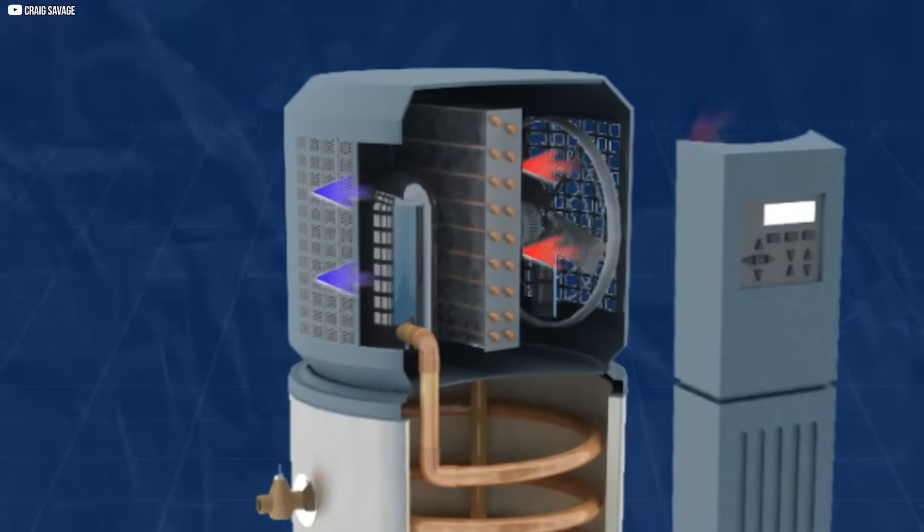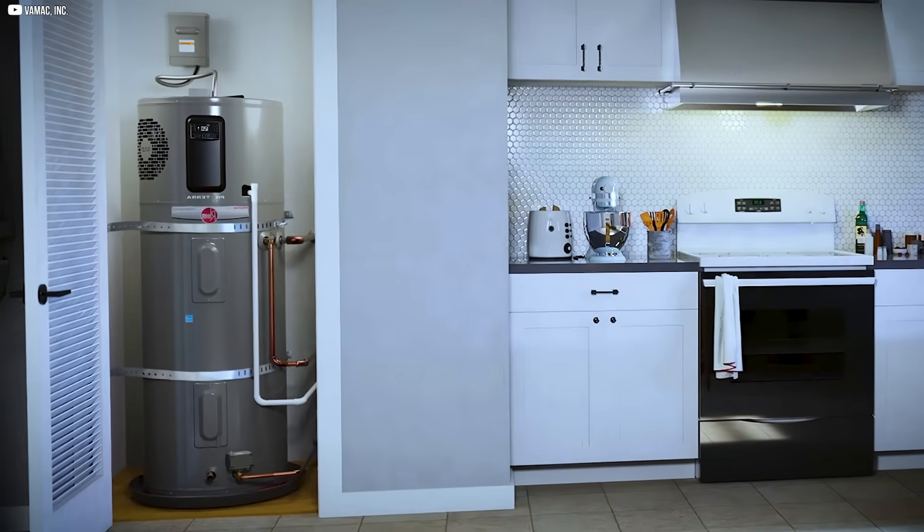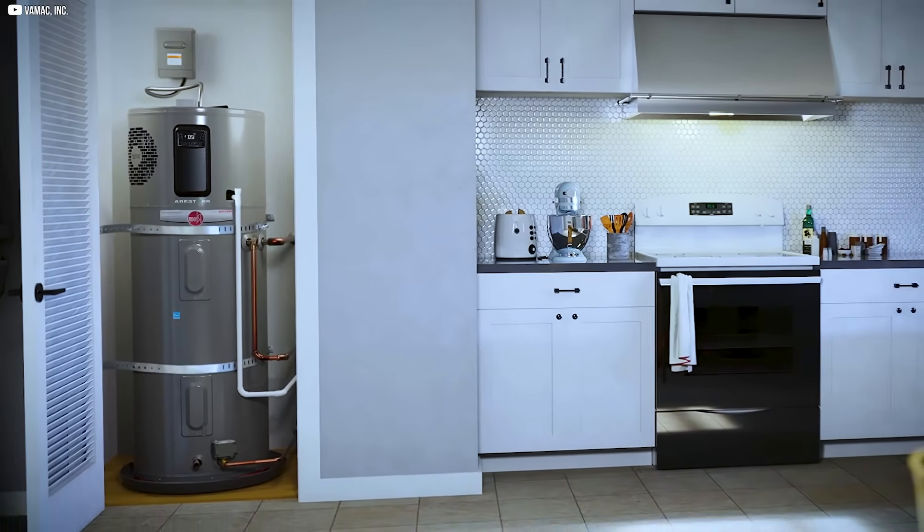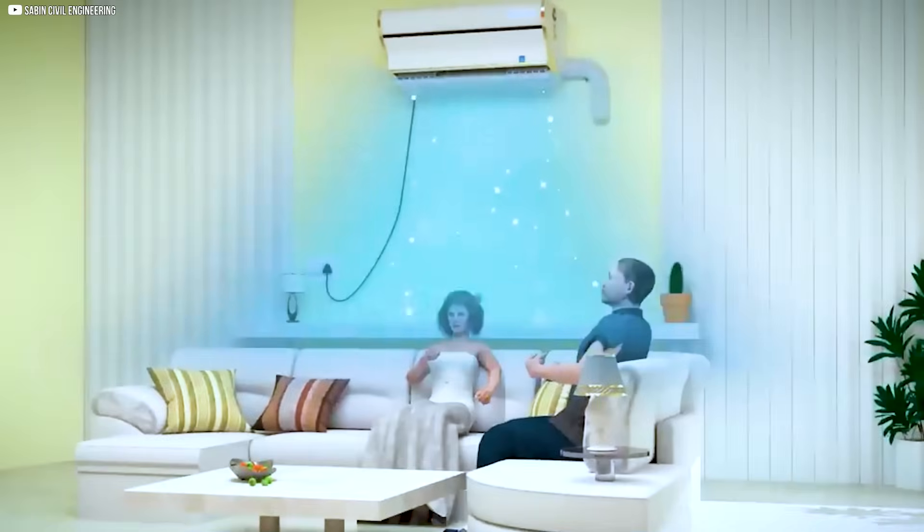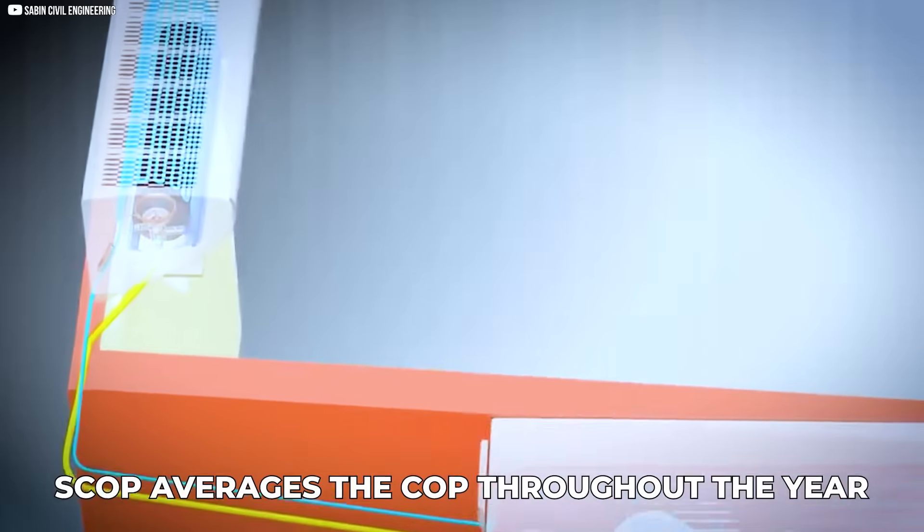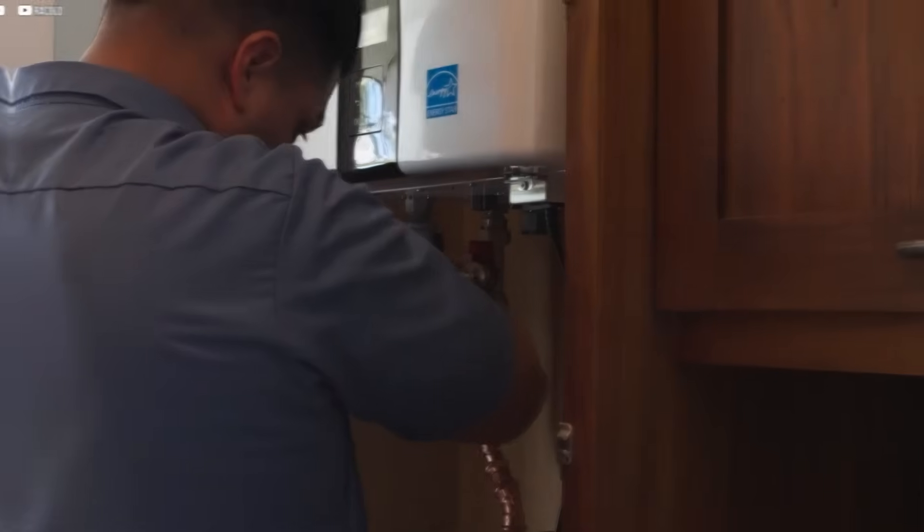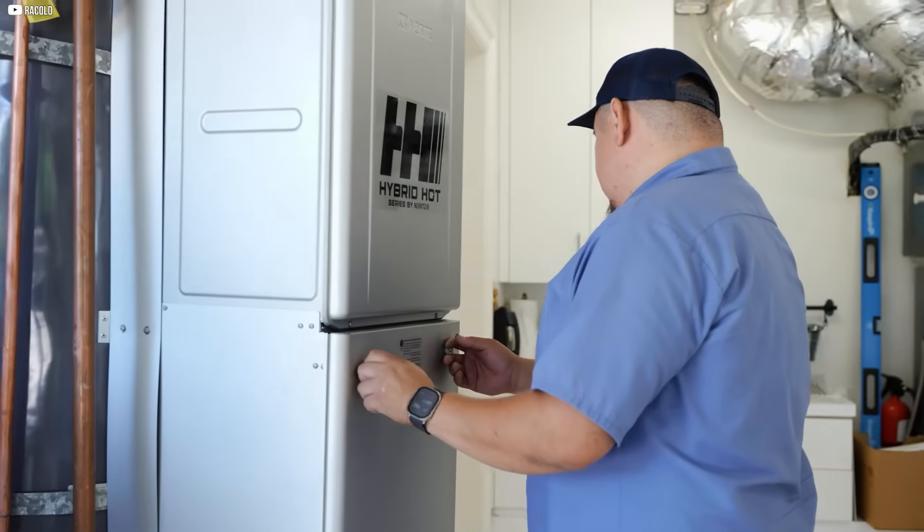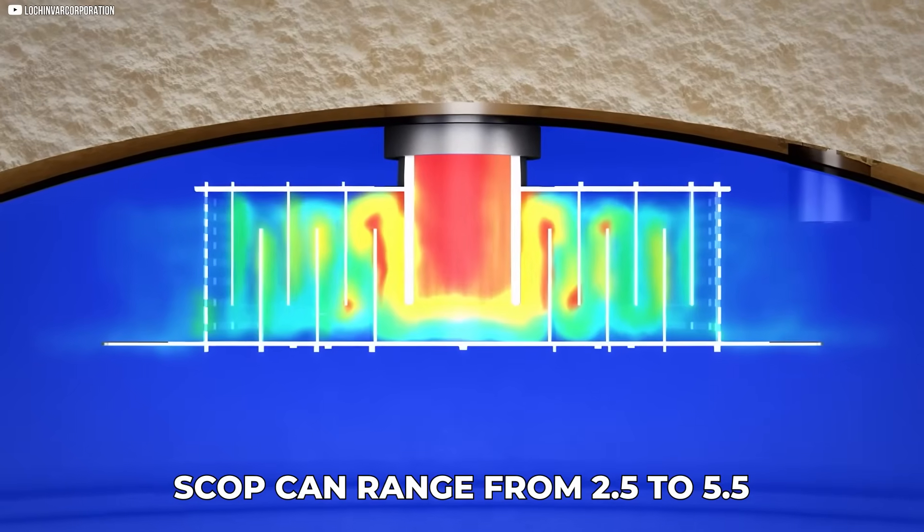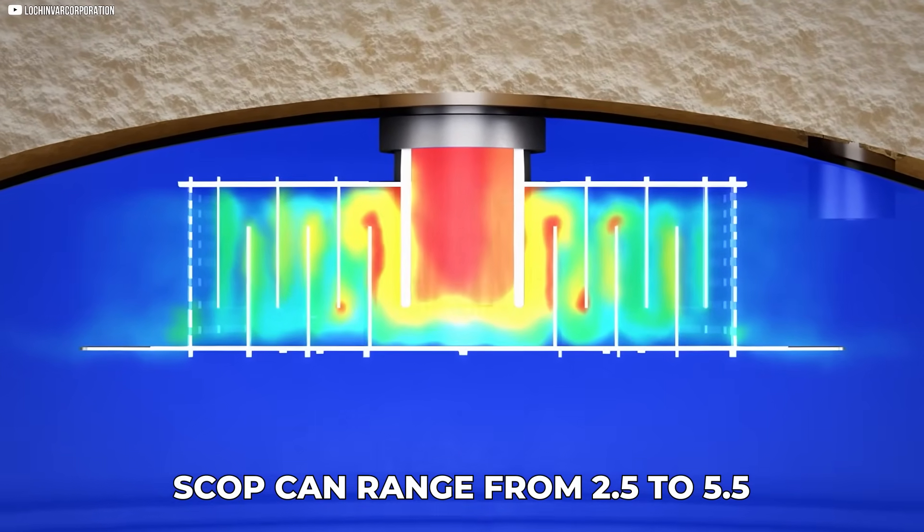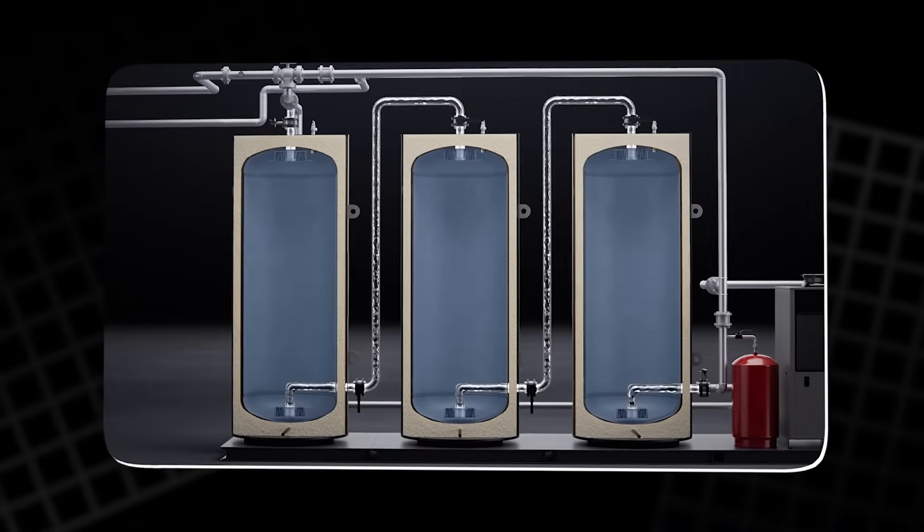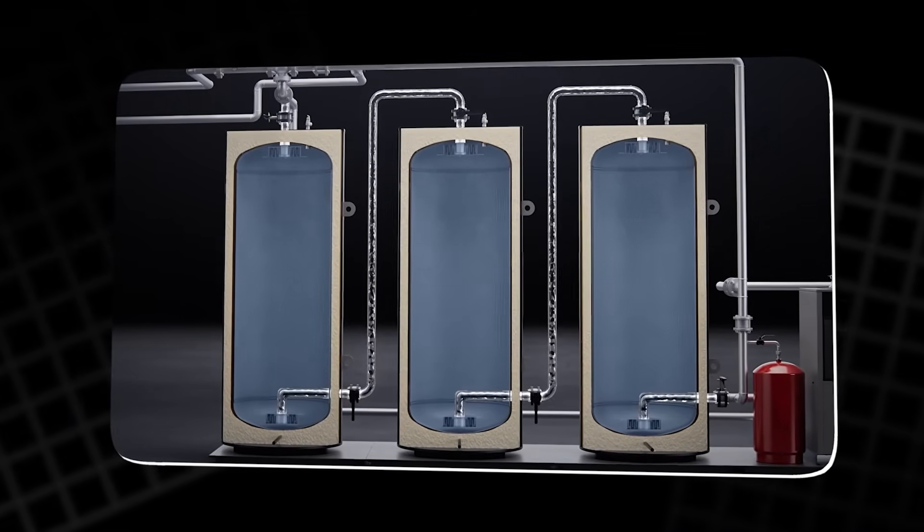However, there's another important metric called SCOP, or Seasonal Coefficient of Performance, which takes into account seasonal temperature fluctuations. SCOP averages the COP throughout the year, reflecting real-world performance. Depending on factors like the type of heat pump and installation, SCOP can range from 2.5 to 5.5, making heat pumps significantly more efficient than traditional gas boilers.